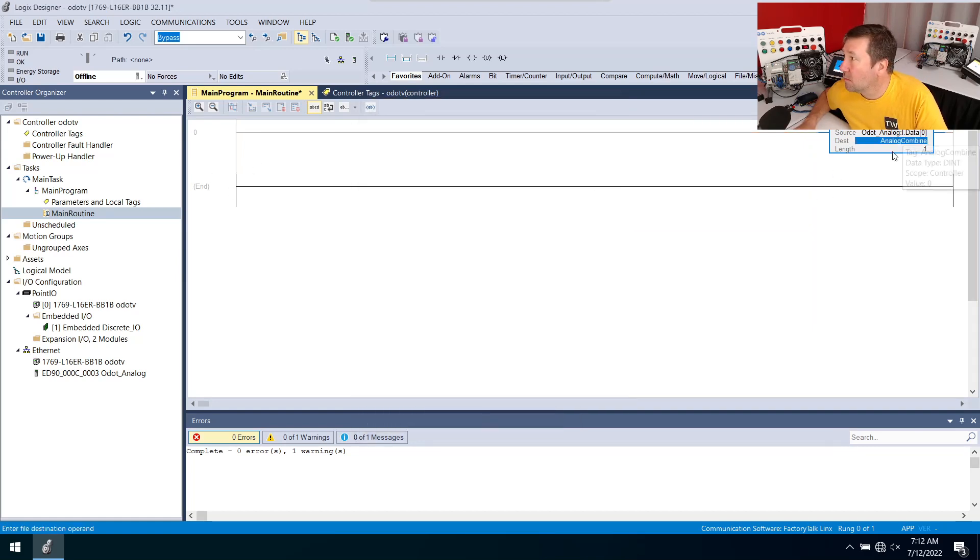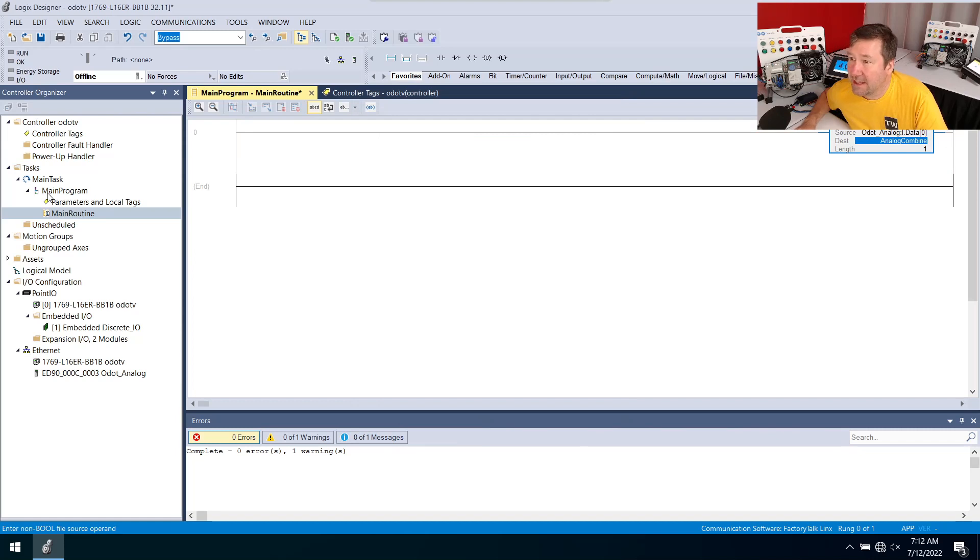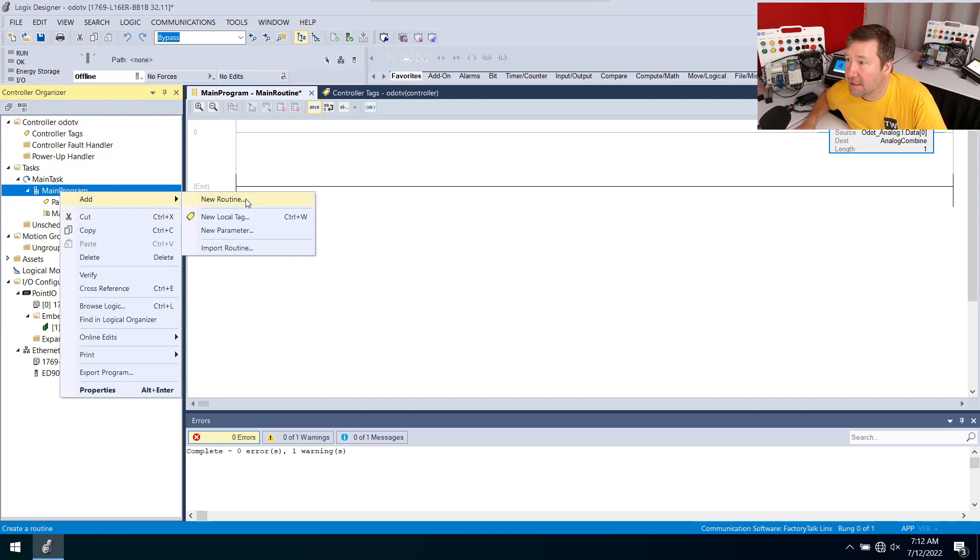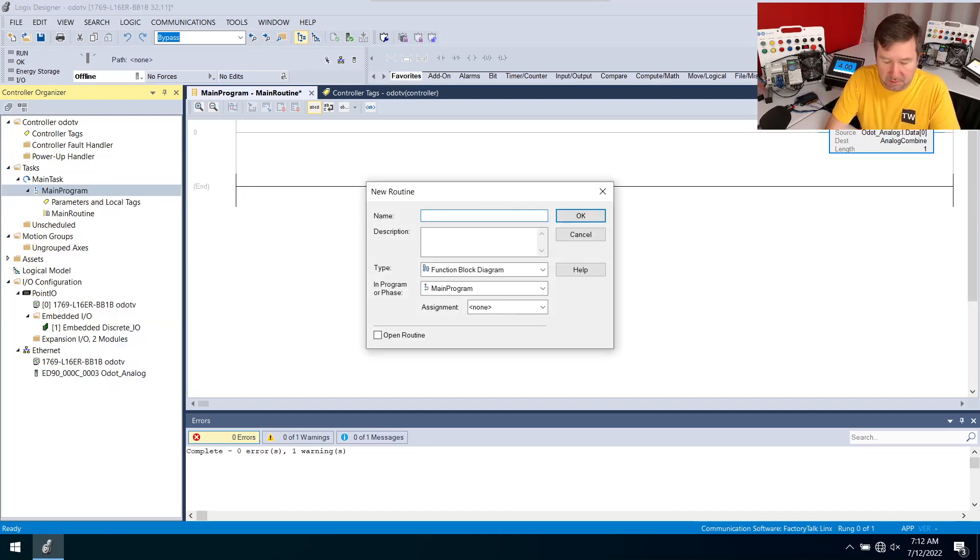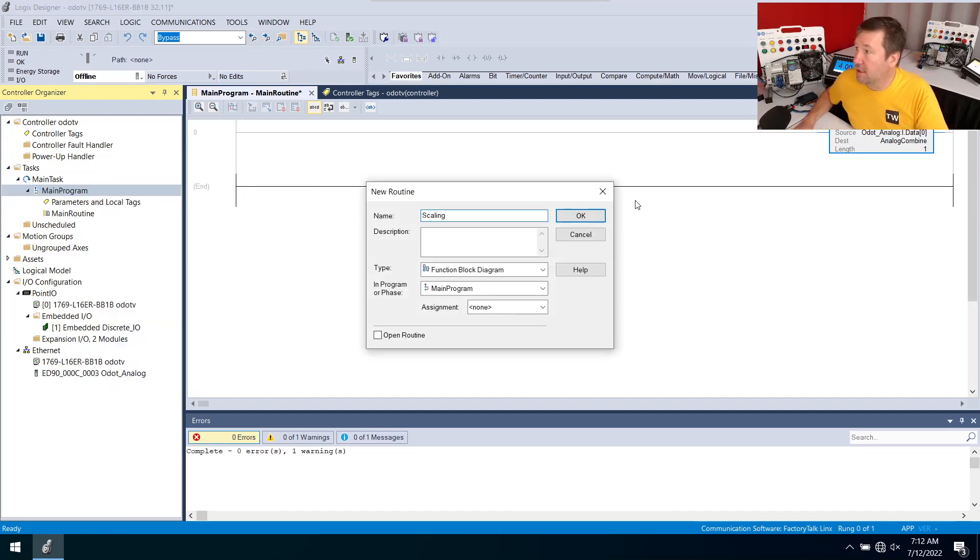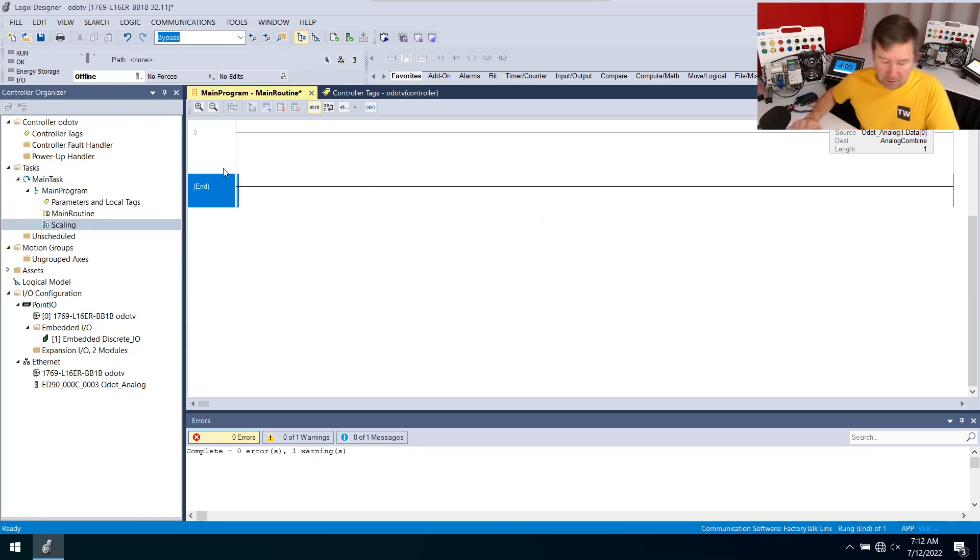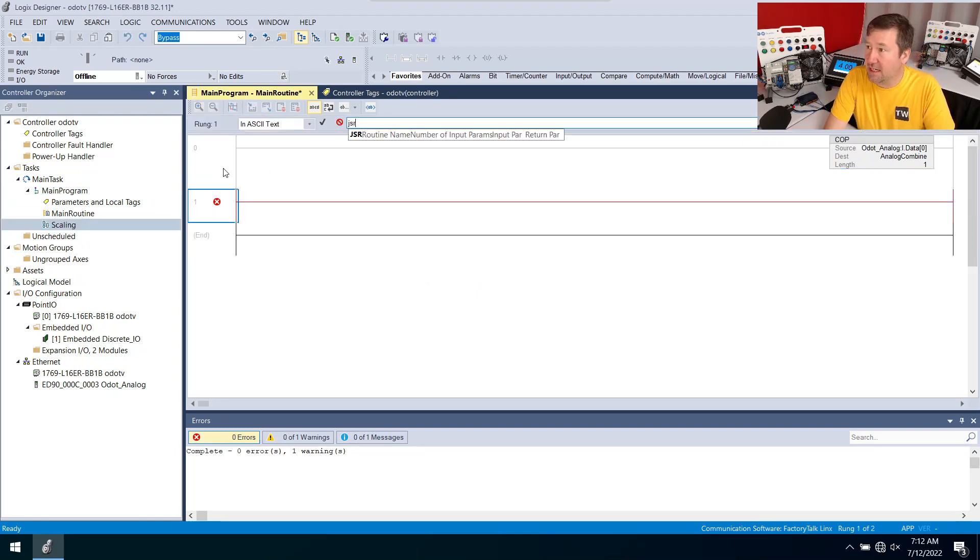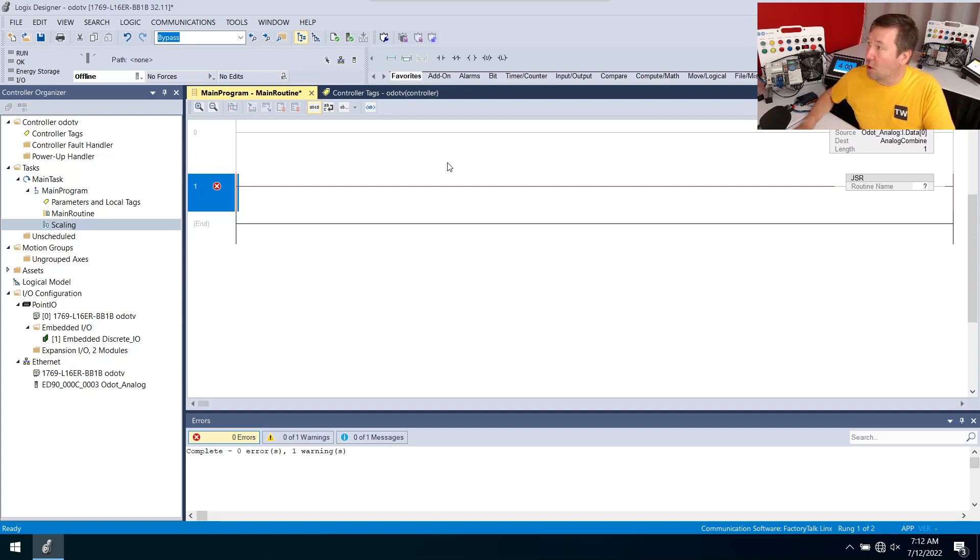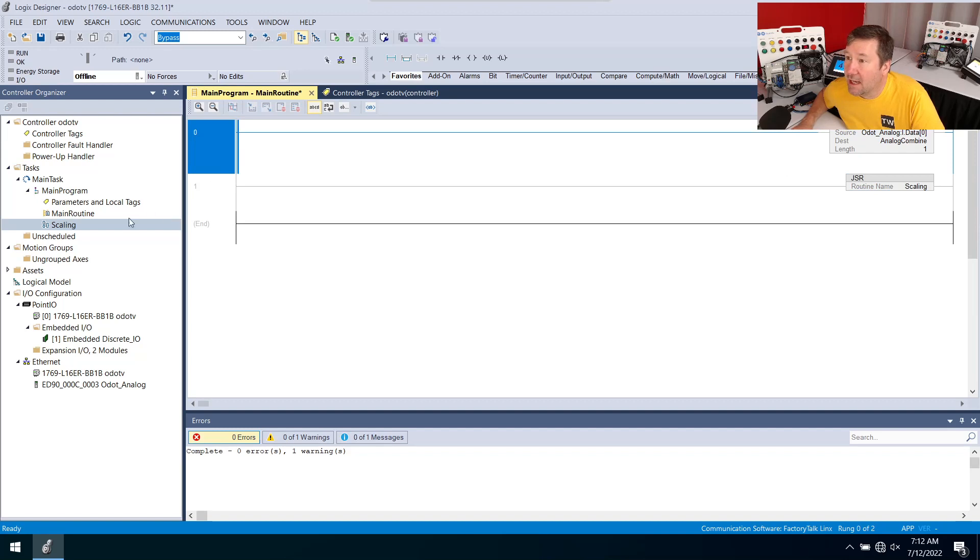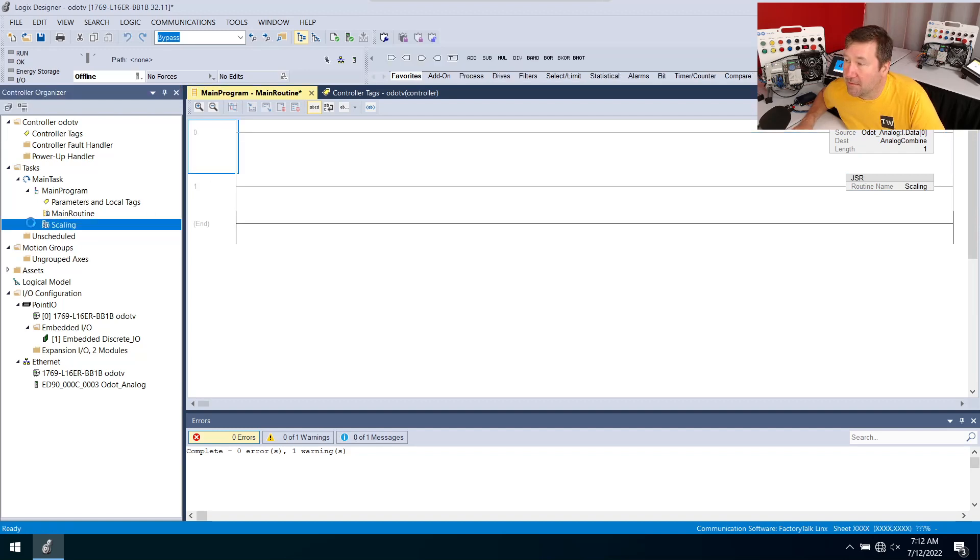Now we're going to scale this. I like doing the scale in either function block or structured text so I'm going to right click the main program, add new routine. This will be my scaling and it will be a function block diagram. While we're at it in our ladder I'm just going to click on this end and type JSR for our jump subroutine and we are going to jump to the scaling.